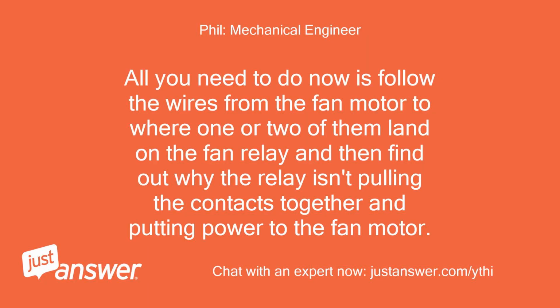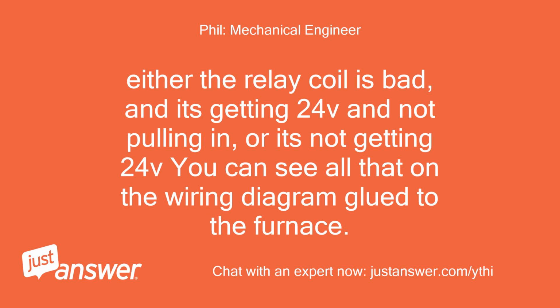All you need to do now is follow the wires from the fan motor to where one or two of them land on the fan relay and then find out why the relay isn't pulling the contacts together and putting power to the fan motor. Either the relay coil is bad, and it's getting 24V and not pulling in, or it's not getting 24V. You can see all that on the wiring diagram glued to the furnace.